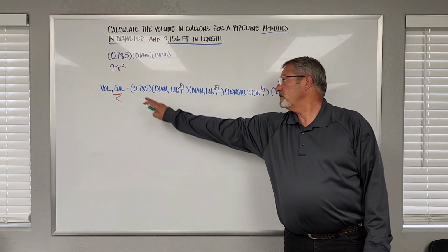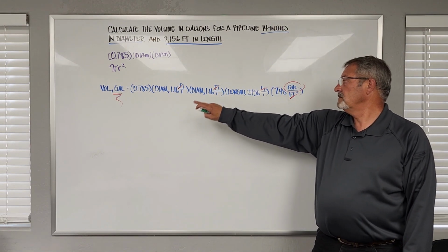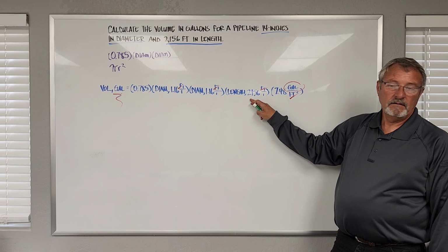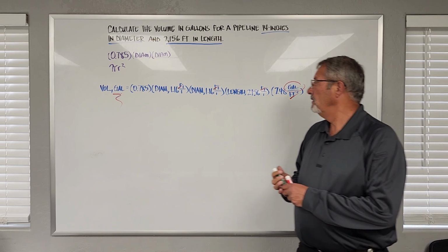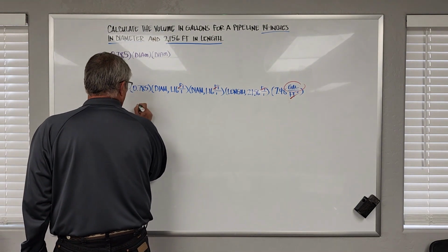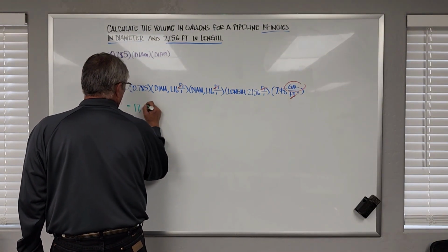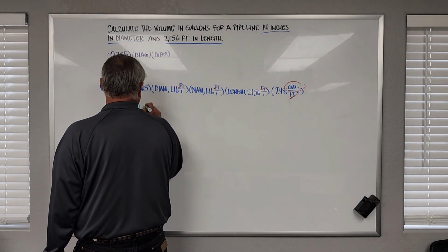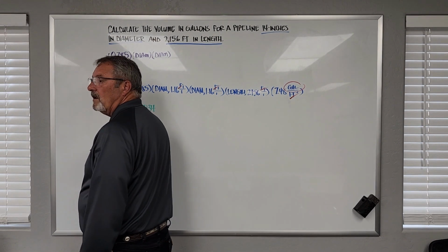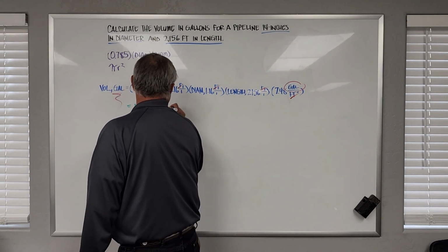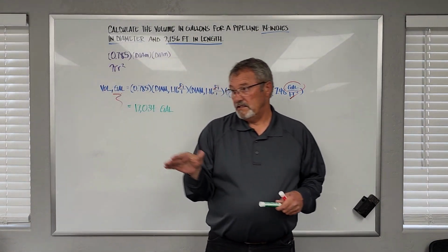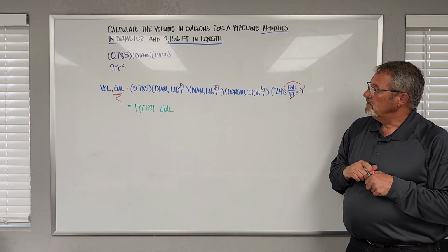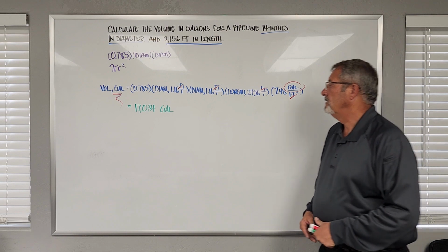All right, somebody multiply 0.785 times 1.16 times 1.16 times 2,156 times 7.48. You get 17,034.75 if you want to put that in there. I just heard you mumble 17,000 what? 17,034. 17,034 what? Gallons. Please get in the habit of using the unit of measure so that you're thinking that way. Everybody agrees with that number? Edward? Yes, sir. Nice.